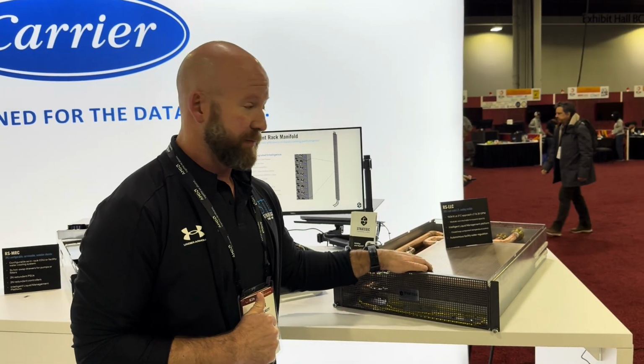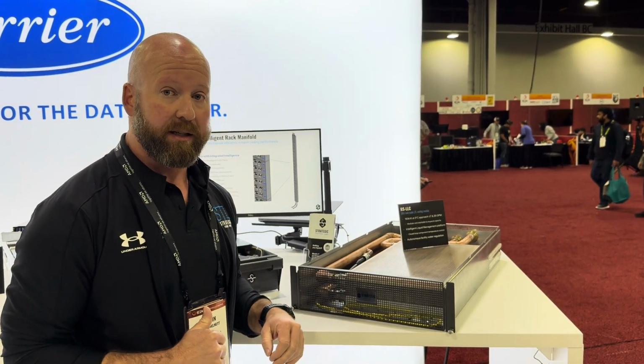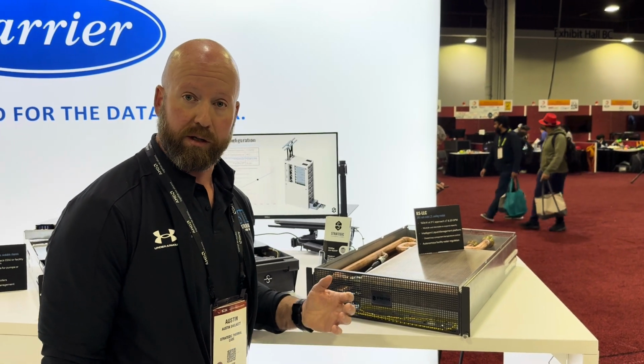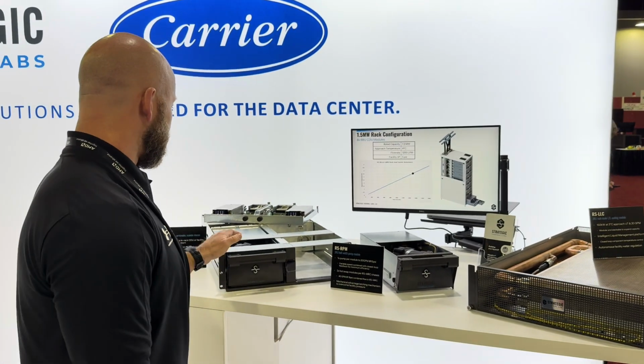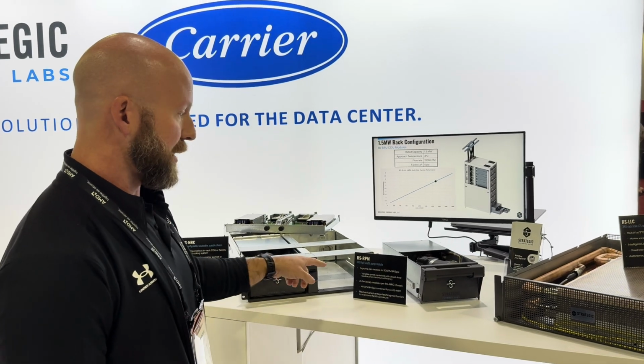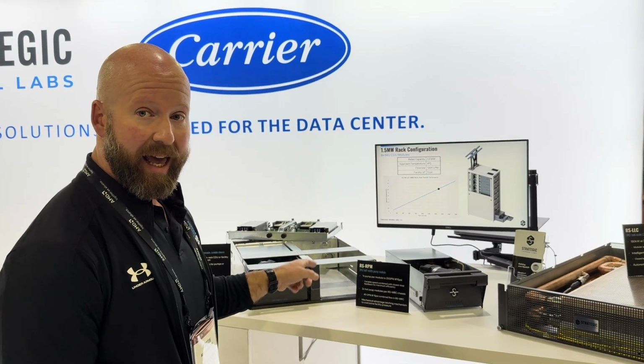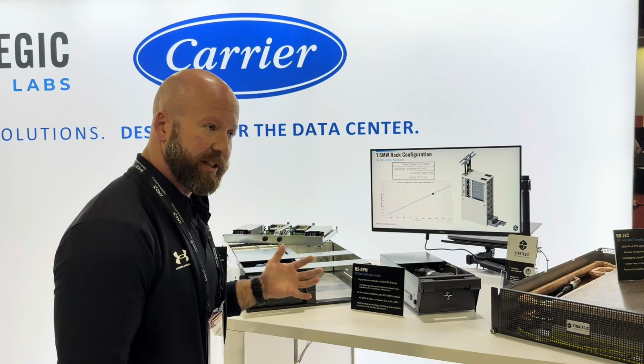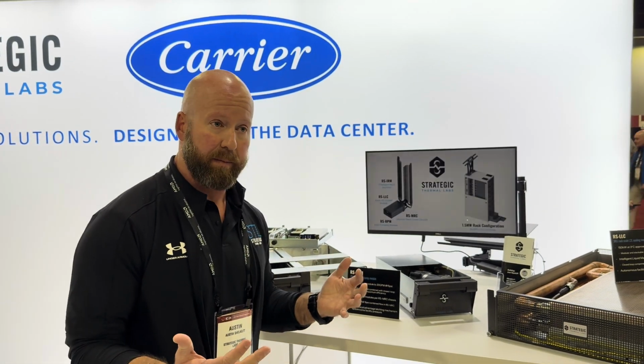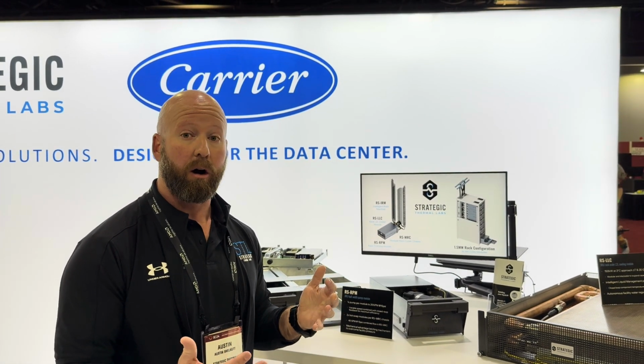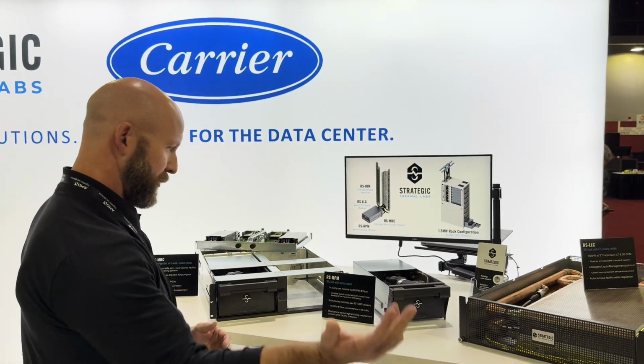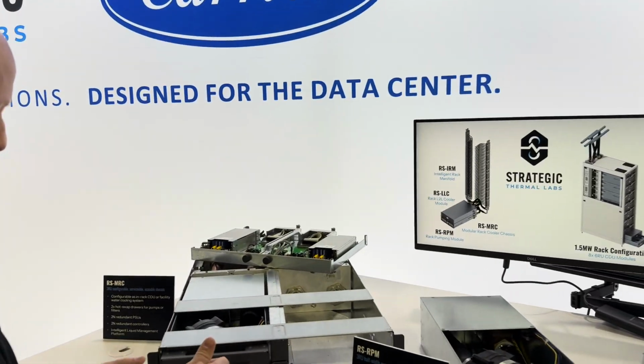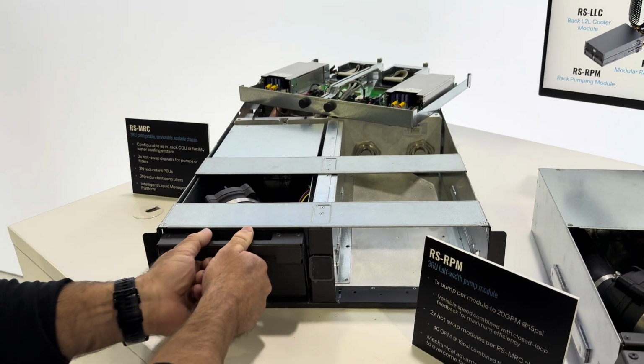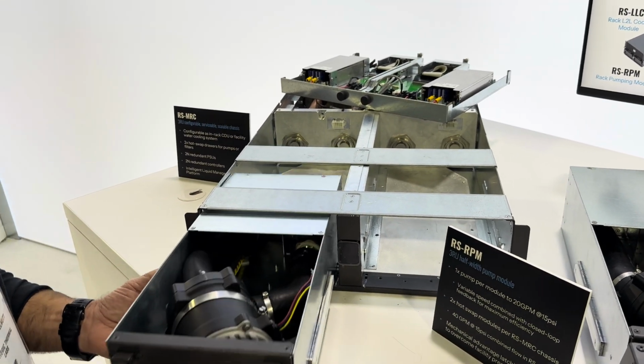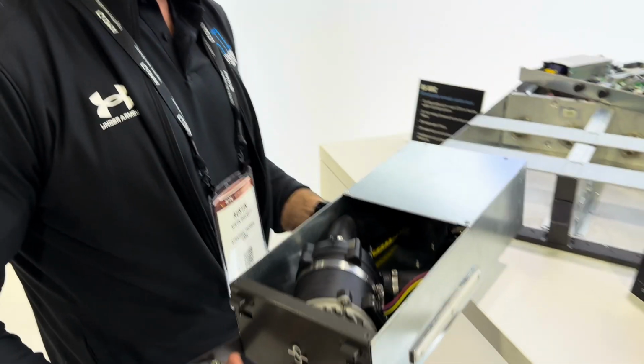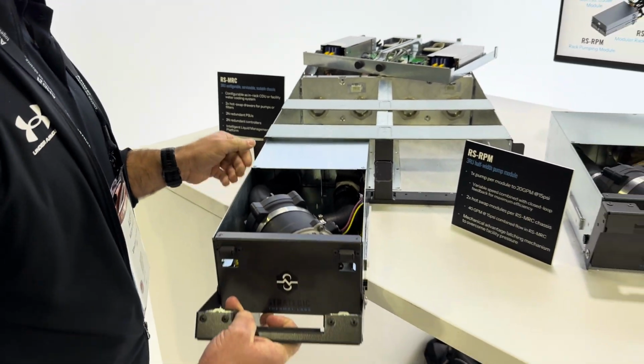The heat exchanger inside this box is rated at 150 kilowatts at a 3 degrees Celsius approach temperature, which is pretty high cooling capacity. On the left side of the pump module, we have 2 pump drawers that are both redundant and hot swappable. A lot of CDU vendors talk about having redundant pumps that aren't necessarily hot swappable or aren't easy to hot swap. If you get a little closer here with me, we'll go through. These pump drawers are extraordinarily easy to pull out. They can be replaced, worked on, whatever the service requirement looks like for the end customer.